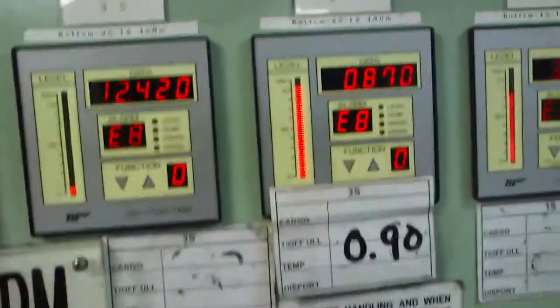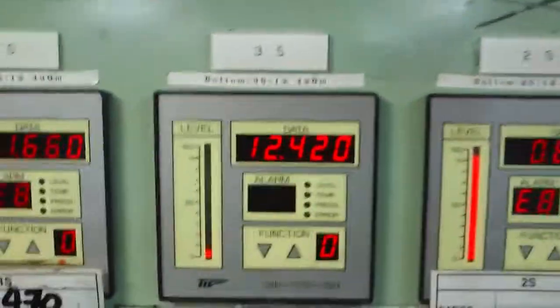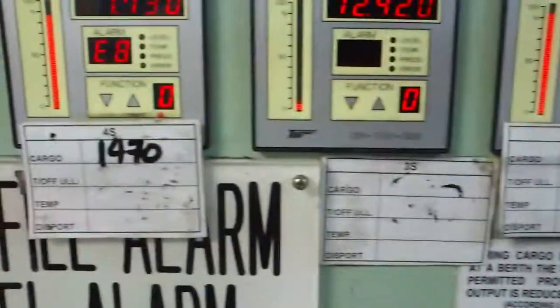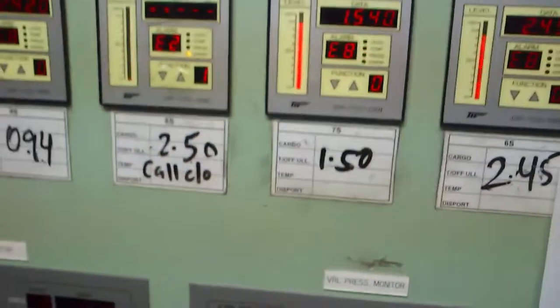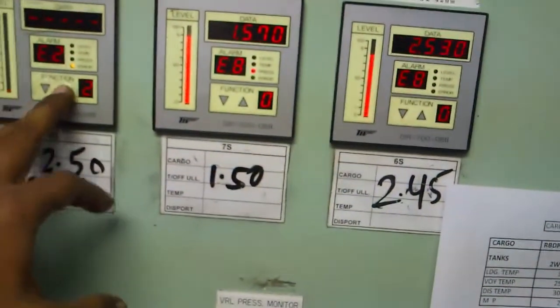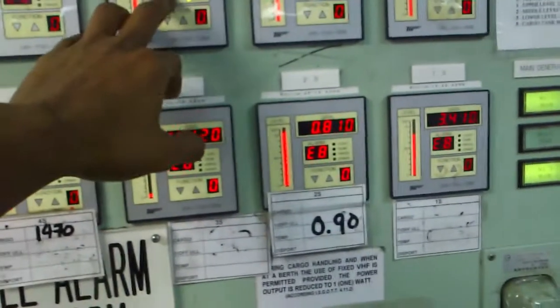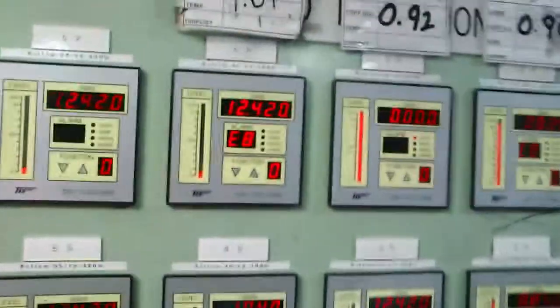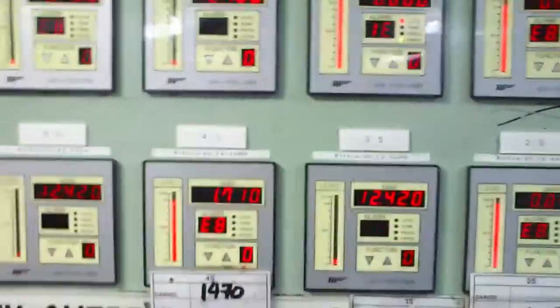So normally E8 errors come when there is moisture in the gauges, sorry in your sensors. If moisture is there in your sensors that time E8 error will come. So if you put any silica in that sensor panel where the sensor panel is there, it will not come. You have to reset the system behind this panel inside the panel. There is a button for resetting to reset switch on switch off. This is also the same for the float gauge error. We have removed the float gauge that's why we're showing zero zero zero zero.